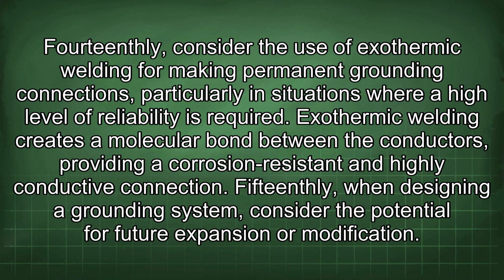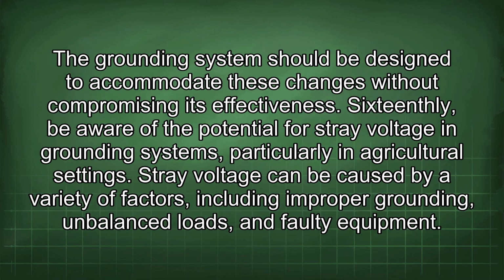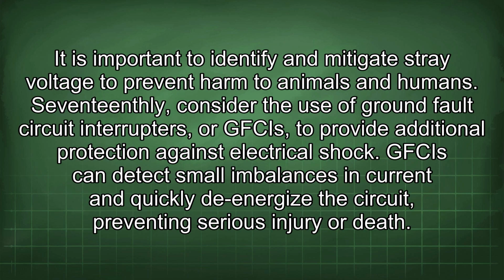15thly, when designing a grounding system, consider the potential for future expansion or modification. The grounding system should be designed to accommodate these changes without compromising its effectiveness. 16thly, be aware of the potential for stray voltage in grounding systems, particularly in agricultural settings. Stray voltage can be caused by a variety of factors, including improper grounding, unbalanced loads, and faulty equipment. It is important to identify and mitigate stray voltage to prevent harm to animals and humans.